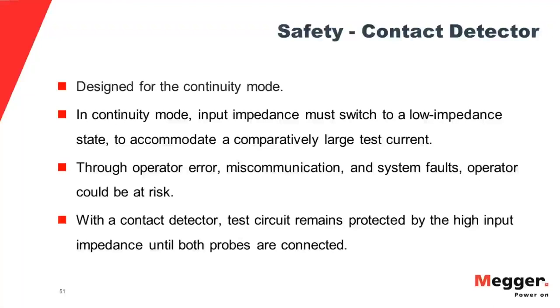A good quality tester with a contact detector will not shift from the input protected insulation range down to the lower resistance continuity measurement range until both leads are connected. The tester knows this, it can sense it. And so you won't have, let's say, a dangling lead or a lead connected to a metal frame while the low resistance continuity range is engaged, in the event that during those few seconds some fault occurs on that line. The operator will not be put at any risk. So that's your contact detector.